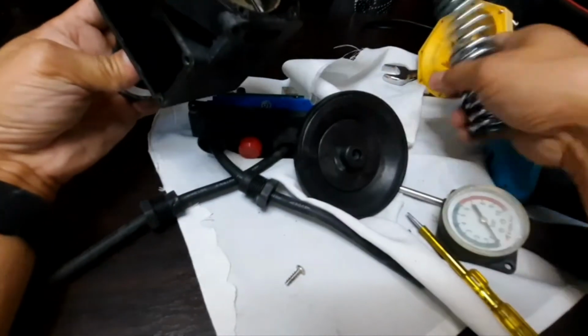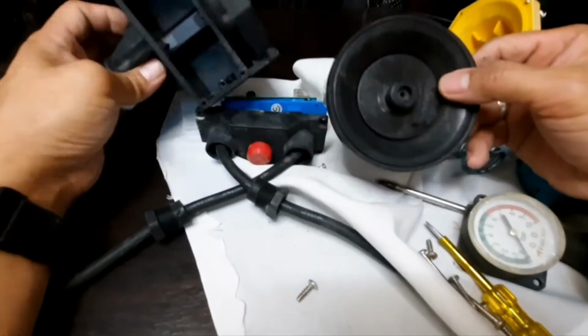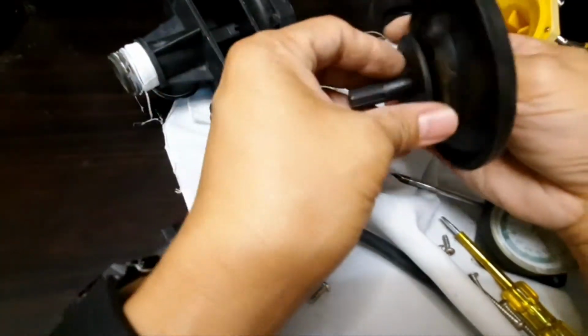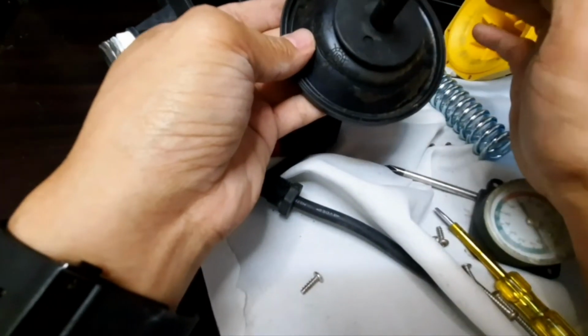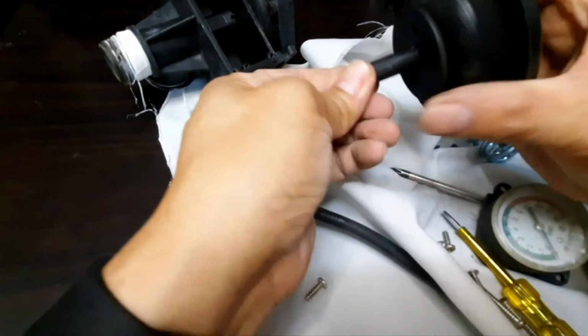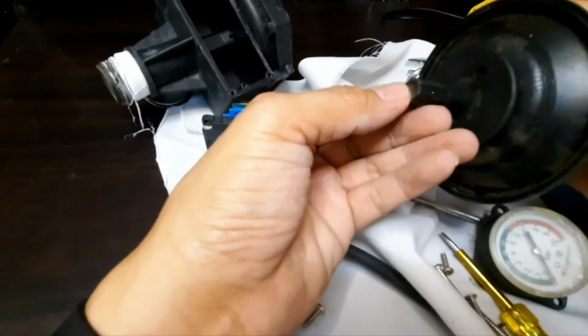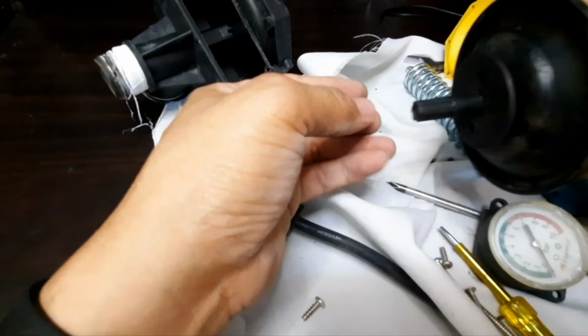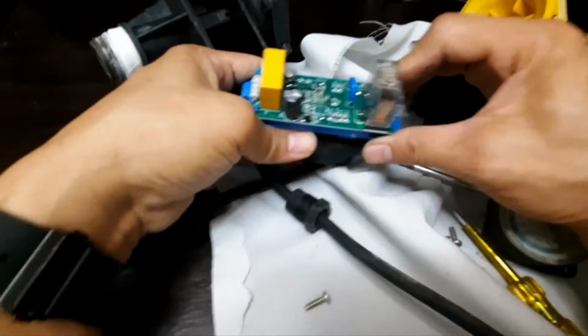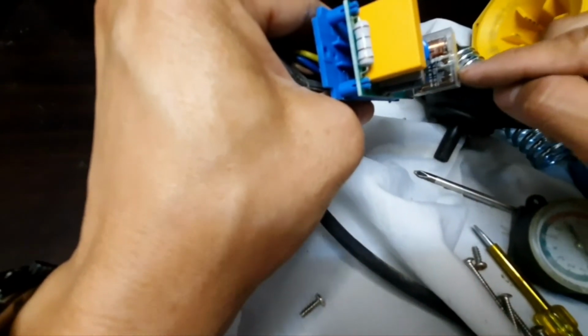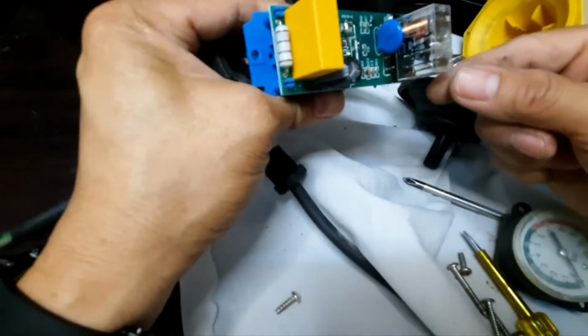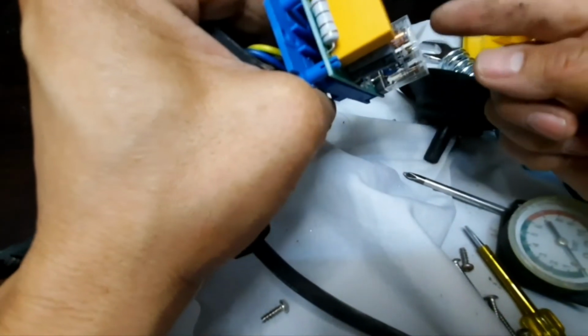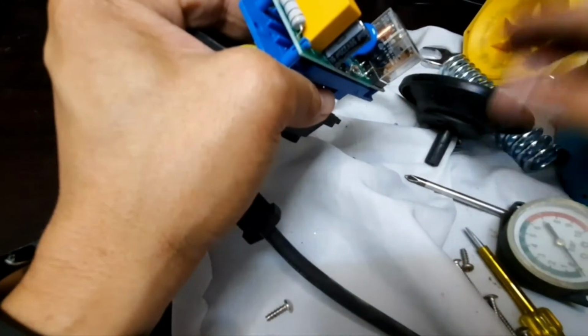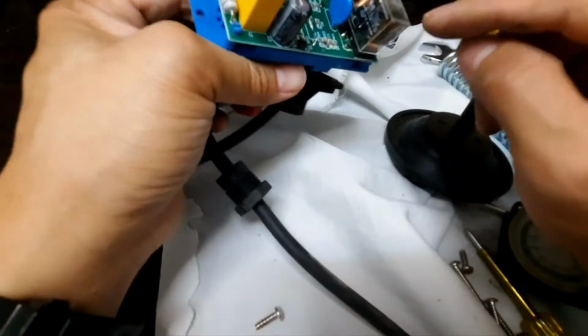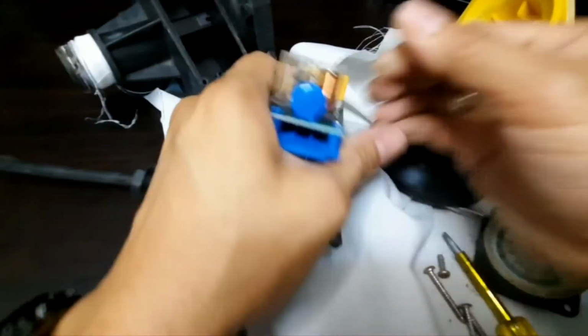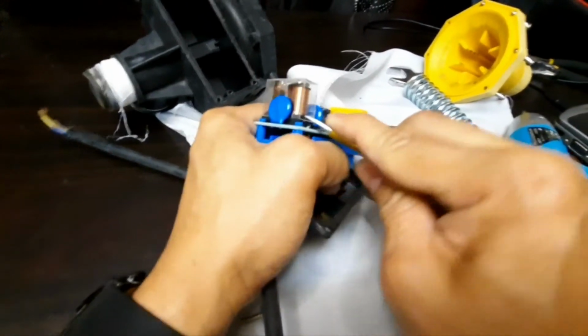Okay, so the common problem for this type of pressure switch is this rubber diaphragm. So if the rubber diaphragm has a tiny hole or cracks, then the system will fail. This magnetic sensor is not going to work accordingly through level or pressure. Okay guys, and the other thing is sometimes this relay, the contact, as you see here, the contact is getting carbonized. So if suppose the pump is not working and the diaphragm is okay, the pressure is there, just simply check and clean this relay. Okay, so practically you can open this relay by opening this cover.